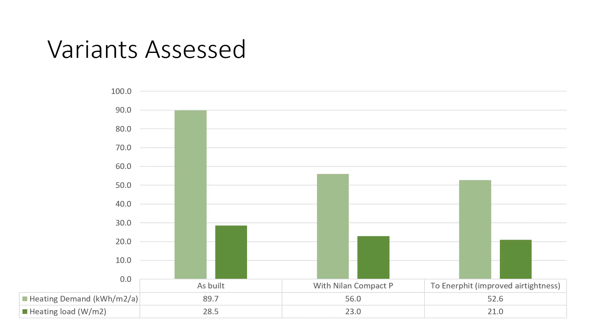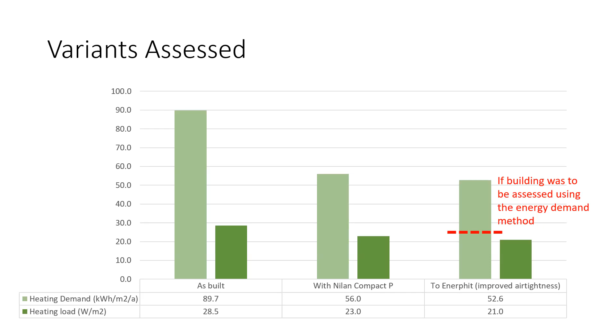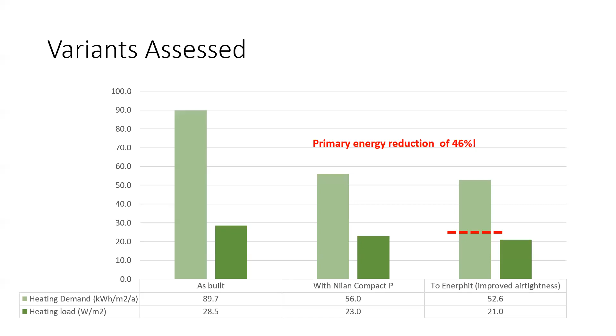And if the building was to be assessed using the energy demand method, you'll see the dashed red line is where your energy demand would need to be. So you can imagine, you've seen all the measures that Joseph has gone through to get the building to a level. What extra levels you would need to get your energy demand down to 25 would be extremely significant, and would likely lead to other issues such as hygrothermal issues or very little usable space left over. And our primary energy reduced by 46% between the as-built and the actual standard being brought to Enerphit. That is primarily because you're using an MVHR system and a heat pump, and you've better air tightness, which is bringing your PER down by 46%.